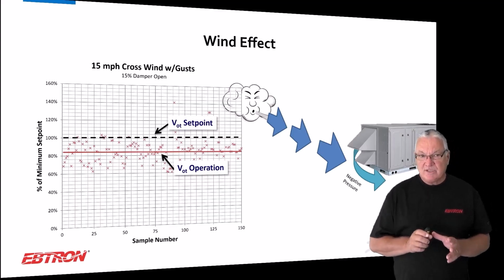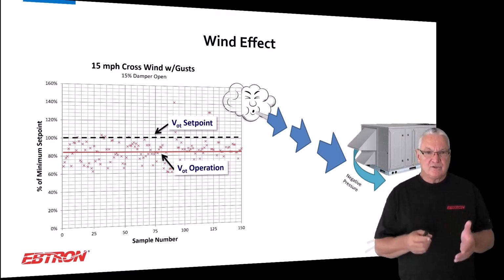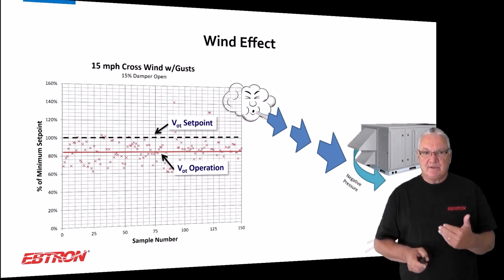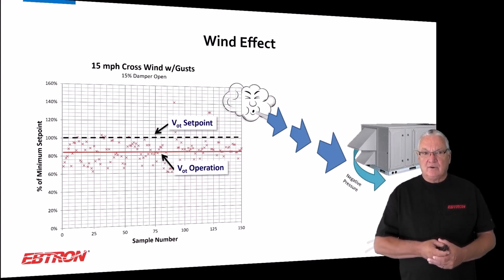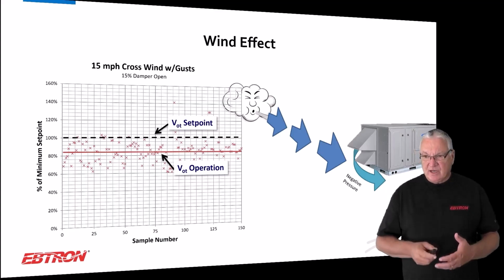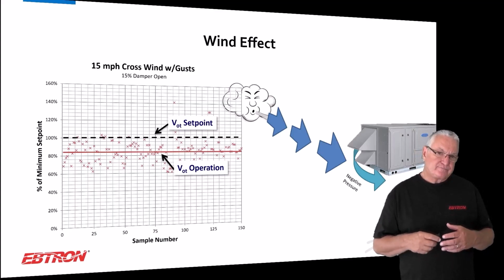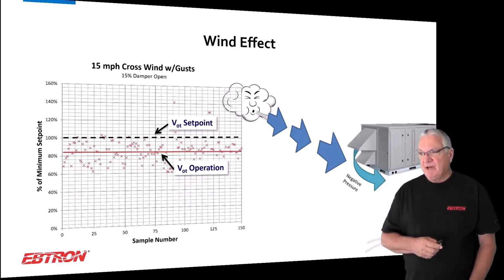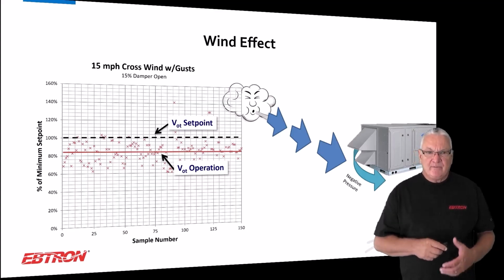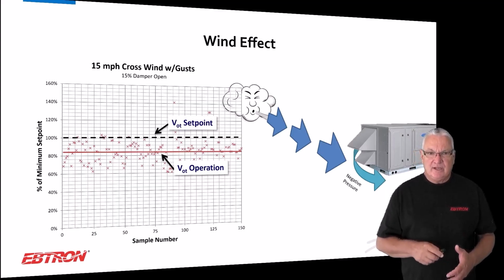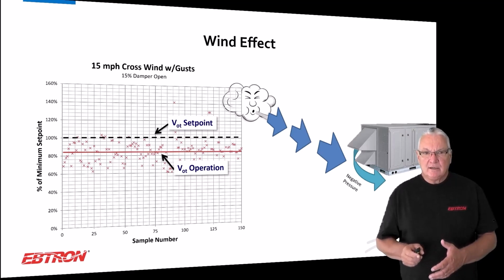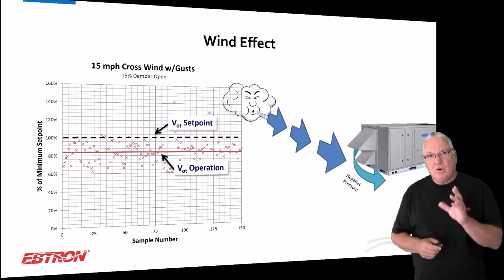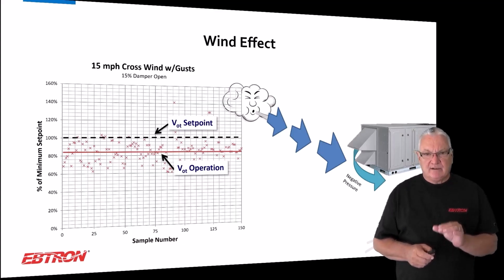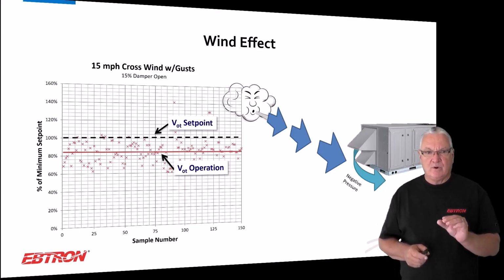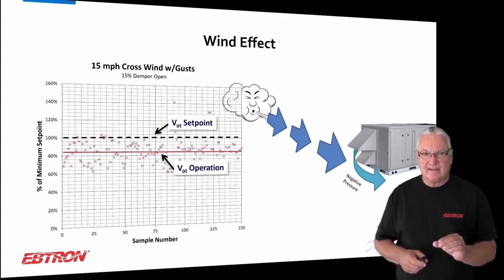And we try to explain to people that are trying to control this that a lot of the errors or problems we see with folks doing outside air control is the output of their control loops are too aggressive, too fast. Slow it down because you can't compensate for these wind pressure changes with an actuator. You want to look at the average flow, and then you want to control to the actual data. And people say to me, "Well, I'm not seeing that on the supply side." It's like, no. The further you get away from the source of the wind, the further you get away from the unit, the air is compressible, so it gets dampened out. You'll see changes, but you won't see them as rapidly. And that's a whole other discussion, and we don't have time to do it today, but there is a right way and a wrong way to take the signal from a flow measuring device and control outdoor air. We're not in an environment where the wind doesn't blow, and we need to not forget that.